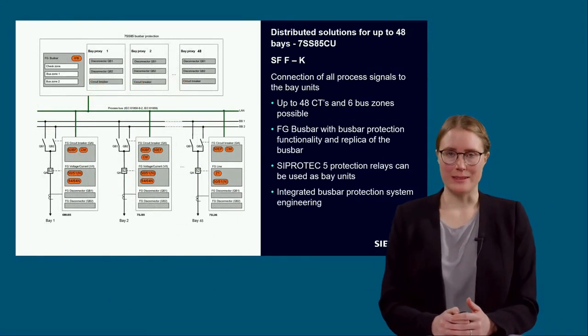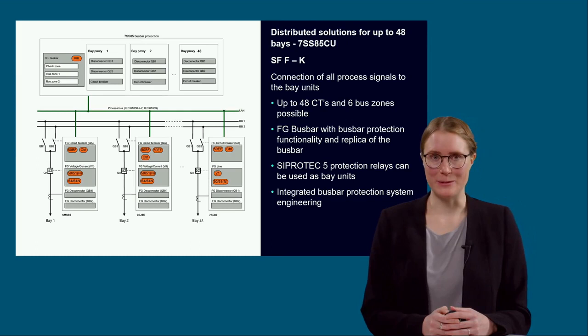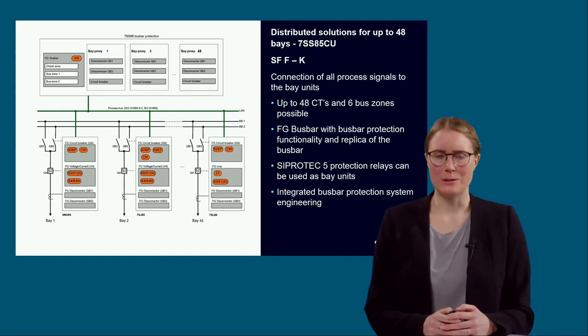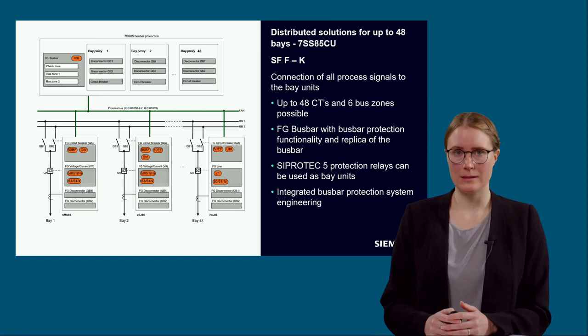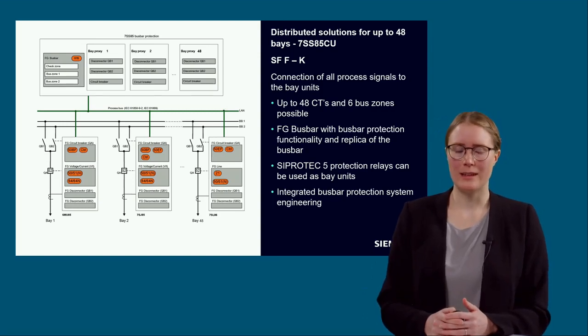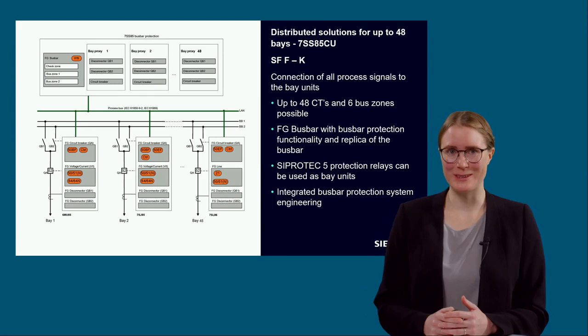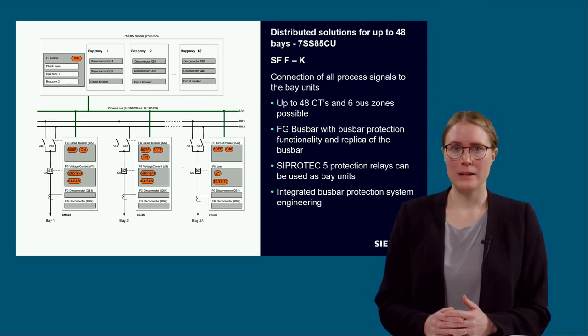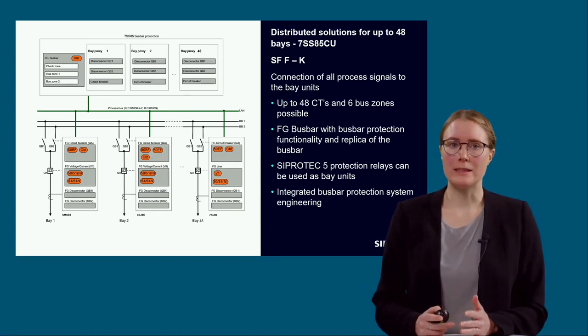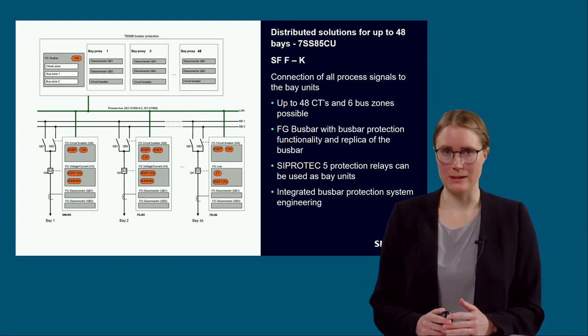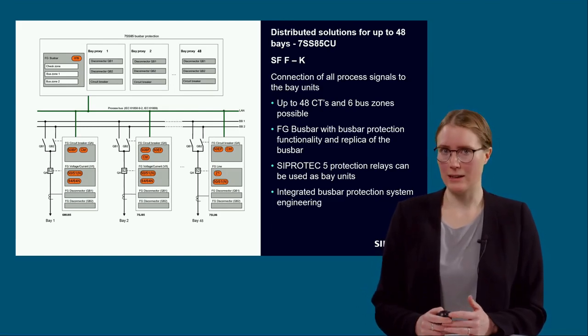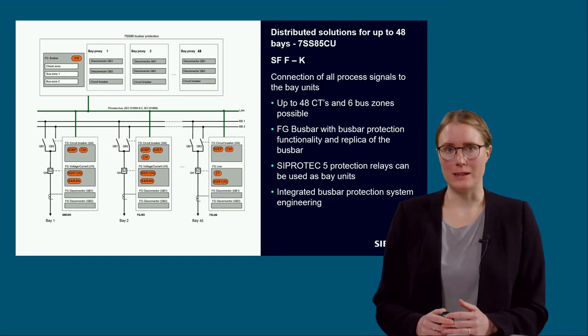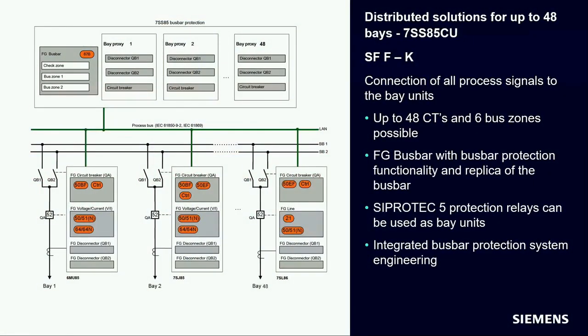This slide now shows the 7SS85CU solution. This is a distributed solution for up to 48 bays. The difference between the centralized solution and the 7SS85CU distributed busbar protection is fundamental. For the centralized and the IEC 61850 compliant solution, you need to create all elements for the busbar differential protection and also nearly all the functionality for the bays in the 7SS85. Single line elements of the bays must be connected to the 7SS85 as well.